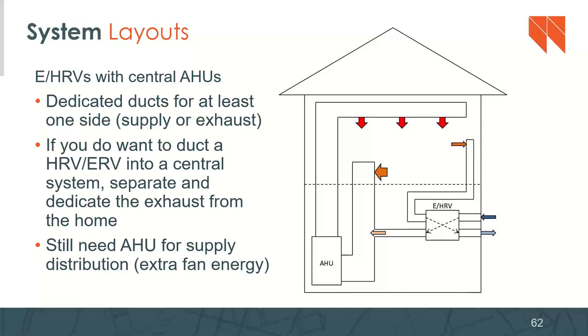We see this quite a bit. So what's happening here is the fresh air from outside is being ducted into the return side of the heating and cooling ductwork, while the exhaust air, the stale indoor air, is being exhausted through a separate duct run. This is sometimes called a hybrid approach to hooking your ERV up to your heating and cooling ductwork. This can be a good way to go. You still need the air handler for supply distribution. That's the downside of this one.